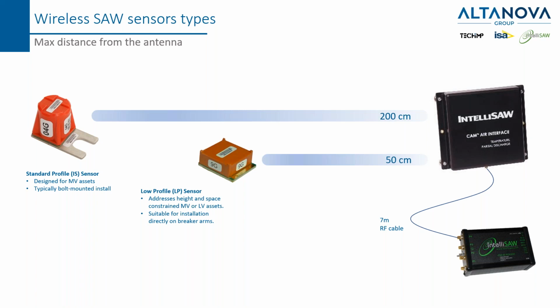There is another sensor, called low profile, addressed to the height and space constraints, as I said, of medium voltage, or even low voltage applications. It is suitable for installation directly on the breaker arms, and it can cover up to 50 centimeters. The reader on the bottom part of this slide is connected through an RF cable to the antenna interface, and it could be a maximum of 7 meters in length.